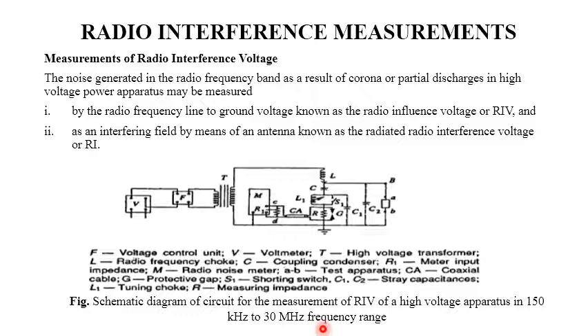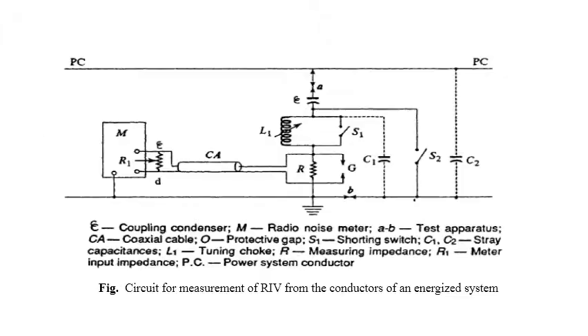Generally the detector circuit consists of diode detectors in series with the circuit resistance RS, charging in parallel to the RC network. The detector is provided with measurement devices to measure either the average value, the peak value, or the quasi peak value. The voltmeter provided at the end of the detector has an input impedance of around 50 ohm to 75 ohm. Then the test circuit for the measurement, the schematic diagram, is shown here.